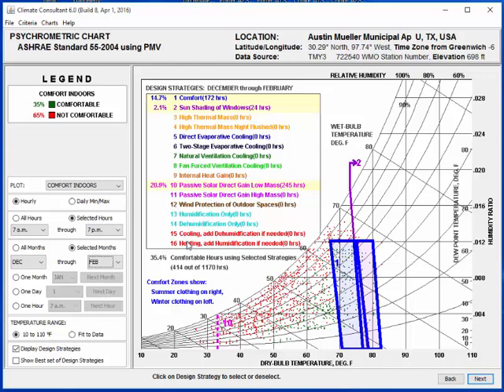Wind protection from outdoor spaces - we're really not interested in these two. Don't turn them on because they are mechanical solutions, and we're trying to look at non-mechanical solutions. Let's look at natural ventilation. If we could ventilate the building, that's 0.2%, so making this a naturally ventilated building doesn't make a whole lot of sense as far as investing in design to do that. Let's try some thermal flushing at night - once again, that's only about 0.2%. The reason is that in Austin, the temperature at night doesn't get that cool. It's totally different for Lubbock or Albuquerque, New Mexico.